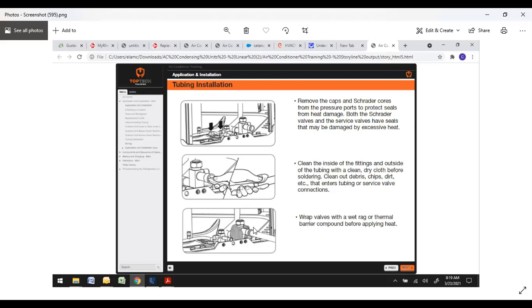I would recommend, number one, you have to use a wet rag of some sort, but I would recommend using a wet rag on each valve and also some thermal heat barrier. So protect those valves. You've got plenty of room there to heat sink it and then wrap those valves. The last thing you want to do is overheat them and replace a set of valves on a brand new unit. It's easy to do if you don't take the right precautions.